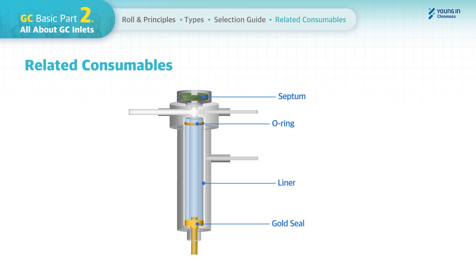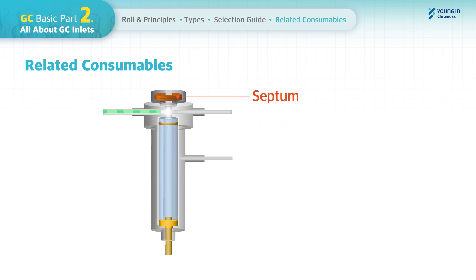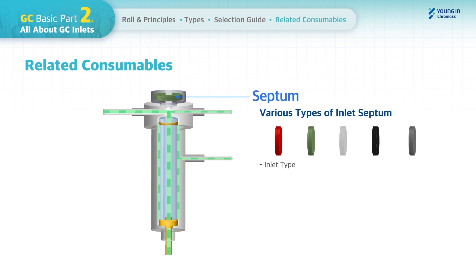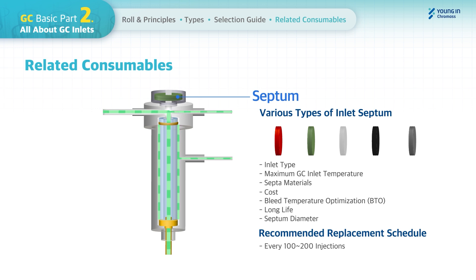There are certain consumables related to GC inlets that can affect GC results. A septum is a thin piece of silicone rubber or similar material located at the top of the GC inlet. It provides a complete seal between the sample injection and carrier gas flow, preventing contamination from outside. Various types of septa exist, differentiated by maximum inlet temperature, material, cost, bleed, temperature optimization, long life, and diameter. It is recommended to replace the GC inlet septum every 100 to 200 injections.